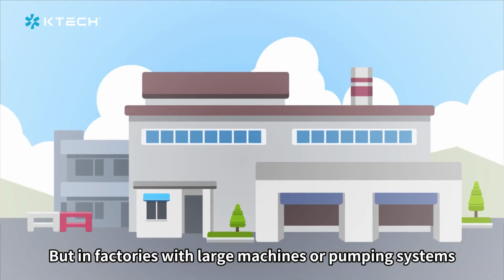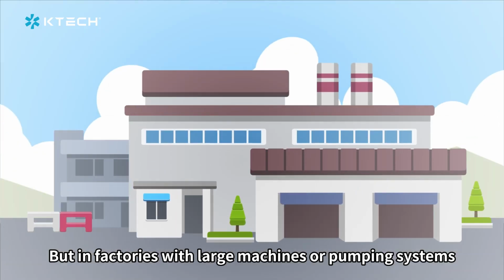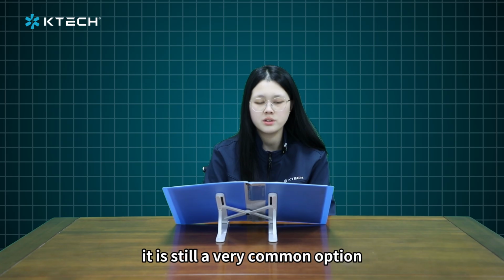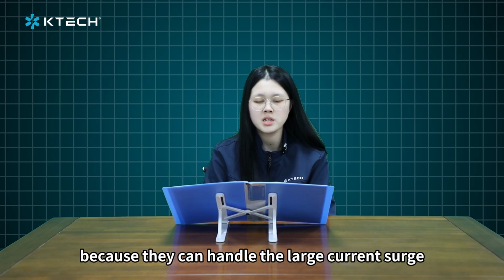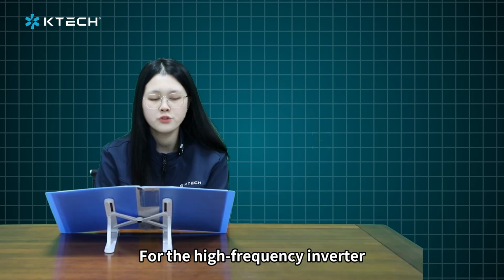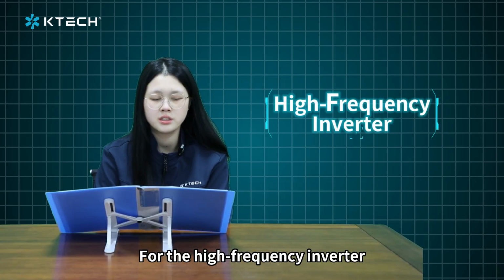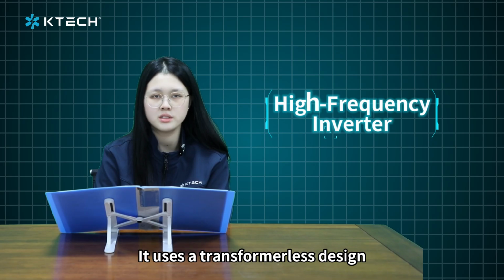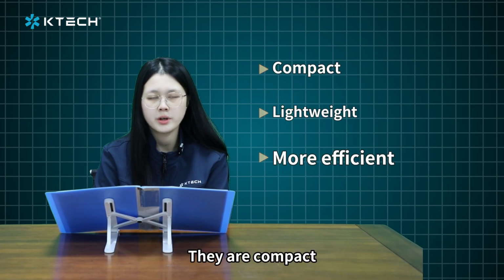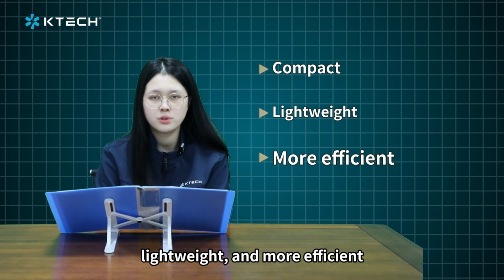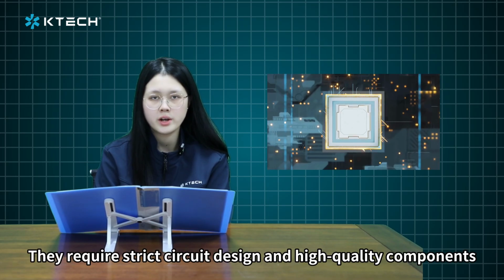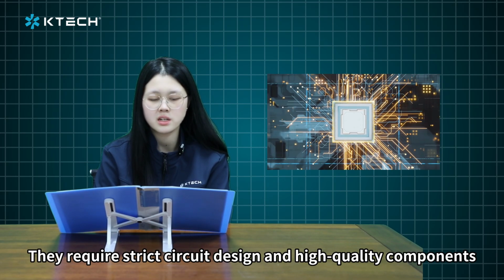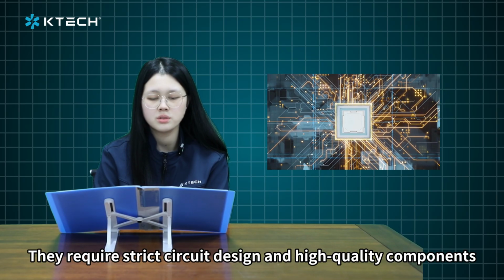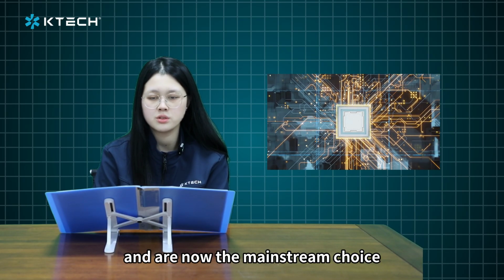But in factories with large machines or pumping systems, it is still a very common option because they can handle the large current surge when motors start. For the high-frequency inverter, it uses a transformerless design. They are compact, lightweight, and more efficient. They require strict circuit design and high-quality components, and are now the mainstream choice.